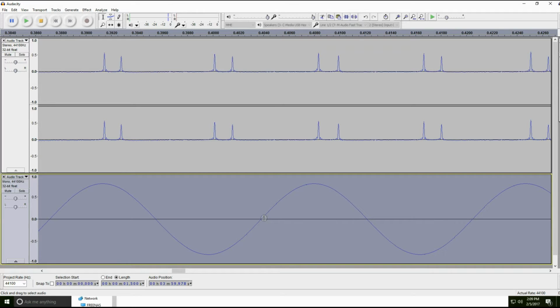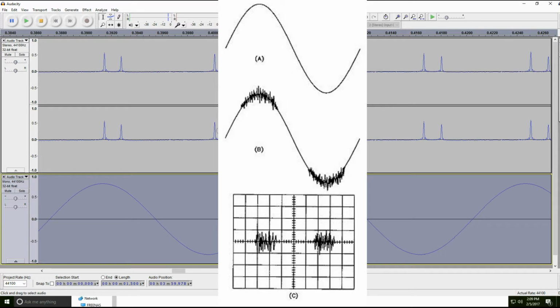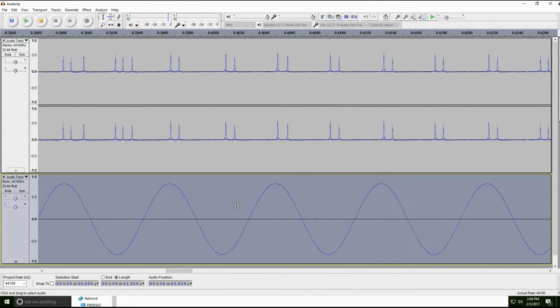So now that we know that that is what's happening and that it is happening at a rate of 120 hertz, and you can tell it's 120 hertz because if this is the beginning of wave one, this is the end of wave one. So it's happening at two times this frequency. This is happening two times for every time it goes from here to here over the period of this. So that tells me this is happening at 120 hertz, which, when we're using a fundamental frequency for hydro of 60 hertz, makes sense because these are the two voltage peaks. Those are the two places that we're going to see some kind of arc or some kind of misbehavior.